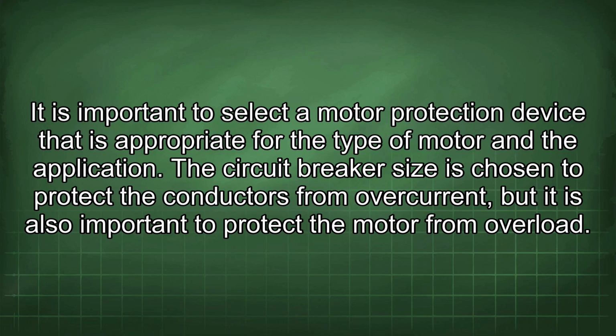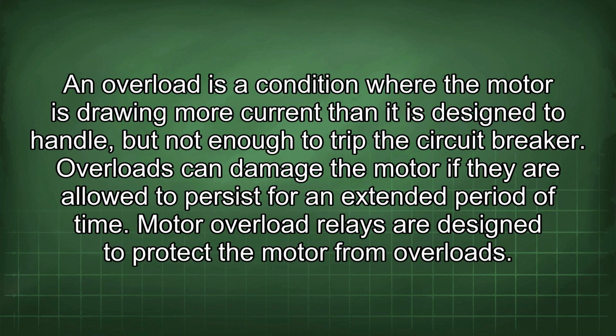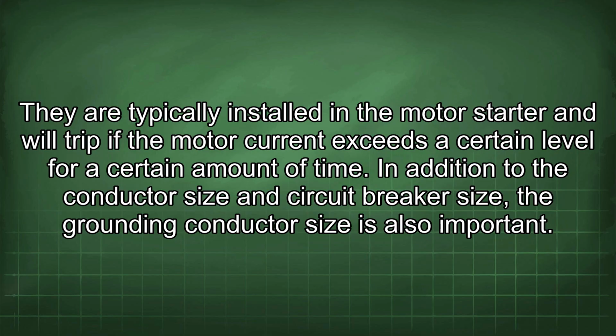The circuit breaker size is chosen to protect the conductors from overcurrent, but it is also important to protect the motor from overload. An overload is a condition where the motor is drawing more current than it is designed to handle, but not enough to trip the circuit breaker. Overloads can damage the motor if they are allowed to persist for an extended period of time. Motor overload relays are designed to protect the motor from overloads. They are typically installed in the motor starter and will trip if the motor current exceeds a certain level for a certain amount of time.